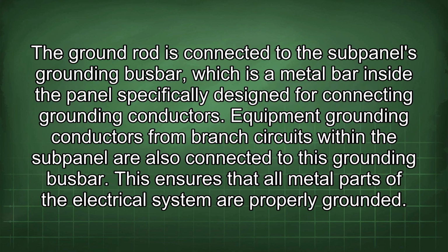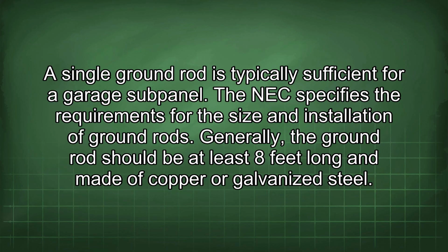The ground rod is connected to the subpanel's grounding bus bar, which is a metal bar inside the panel specifically designed for connecting grounding conductors. Equipment grounding conductors from branch circuits within the subpanel are also connected to this grounding bus bar. This ensures that all metal parts of the electrical system are properly grounded. A single ground rod is typically sufficient for a garage subpanel.